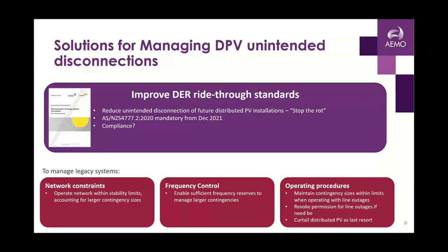I've got this point here on compliance, and I'll get into that in the next slide, but there is a question about the ability to manage compliance to those standards. In the meantime, we also need to manage all those legacy systems, as we've had a lot of PV incorporated into the system. We have already developed some network constraints for some regions, so we change how the network operates and make sure that it's within stability limits. We account for those larger contingency sizes, so we take more reserve and make sure that there are more generators that might help out if that situation were to occur. We've also changed a couple of our operating procedures, making sure that we maintain contingency sizes within limits, and we remove line outages if those are happening on those particular days. And we're working with many networks to look at options where we can curtail distributed PV as a last resort on those events.